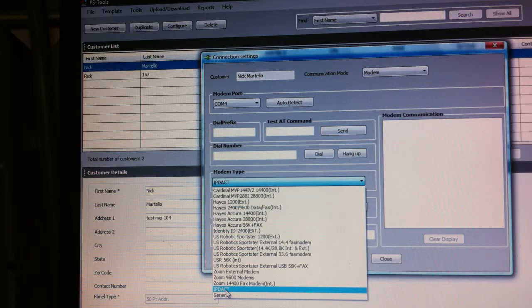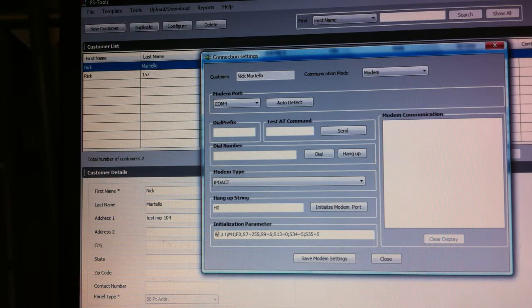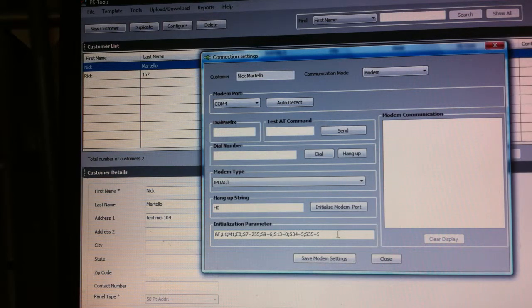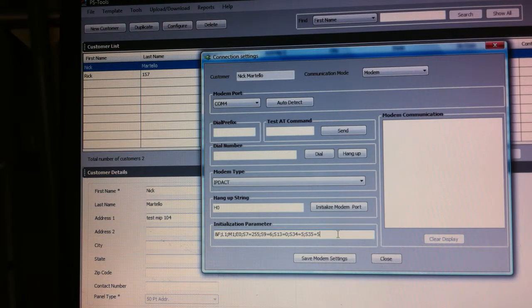The other thing you should do is set up a modem. When you select a modem, pick a generic one, then rename it and save it as IPDACT, because we're going to change some connection strings. Every modem has default connection strings. We want to set some special ones up because most communications are over very long telephone lines, so typically they bump up the volume. We want to reduce the volume and the talk and receive volume on that modem because we're right in the panel, so we don't want to overpower the circuitry in the onboard panel modem.